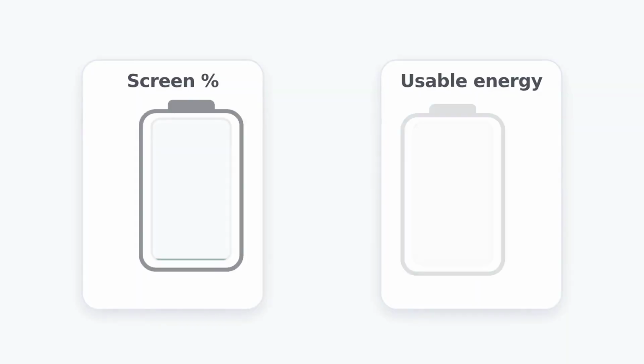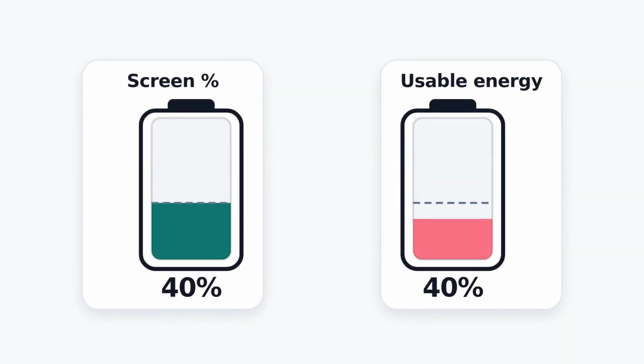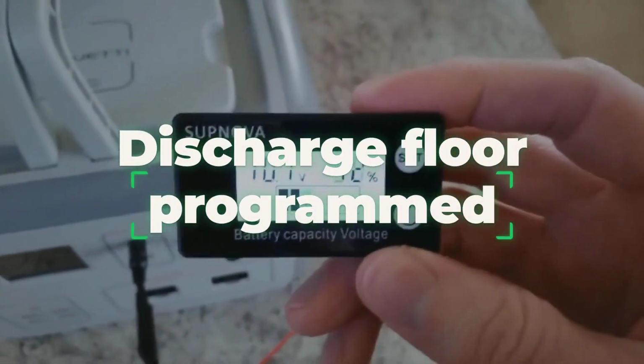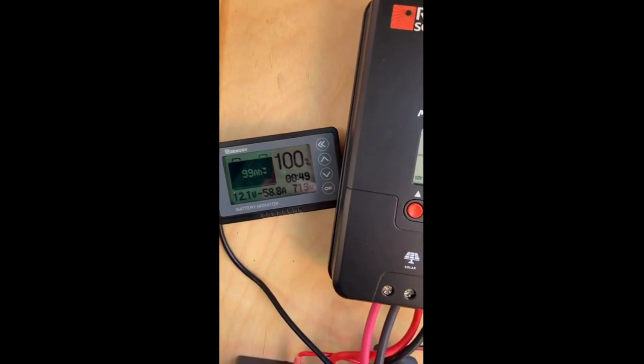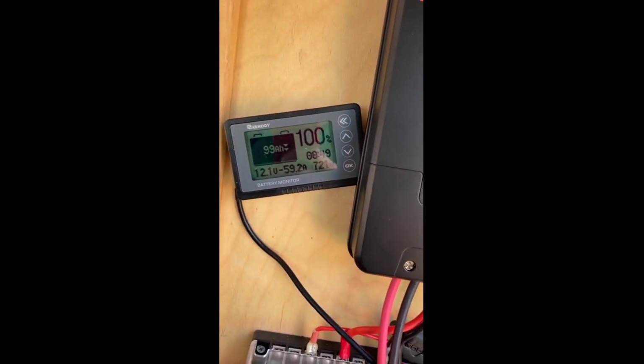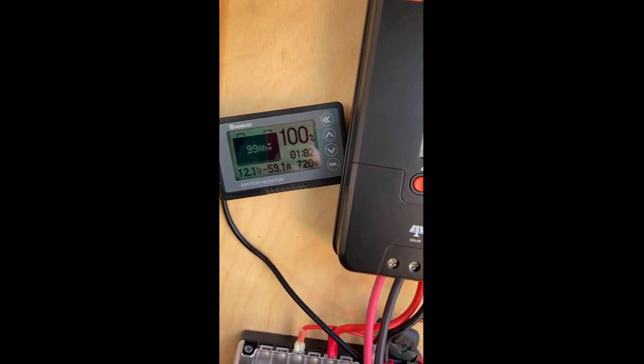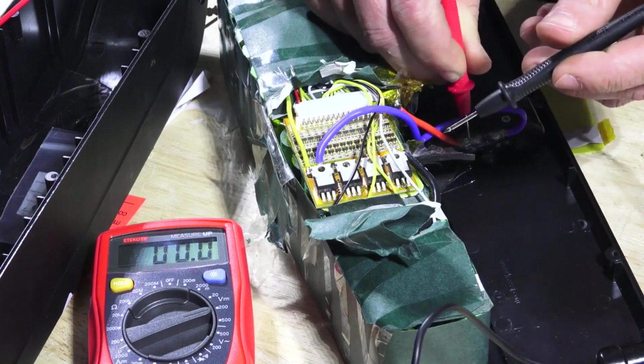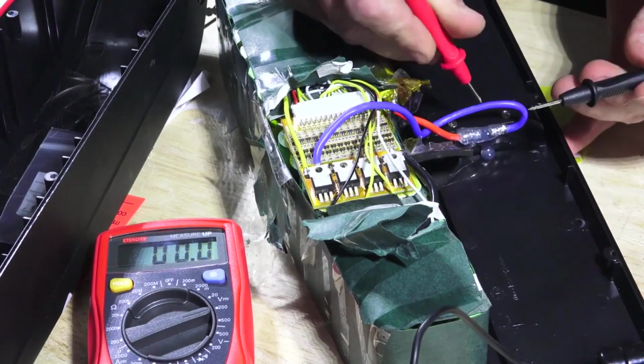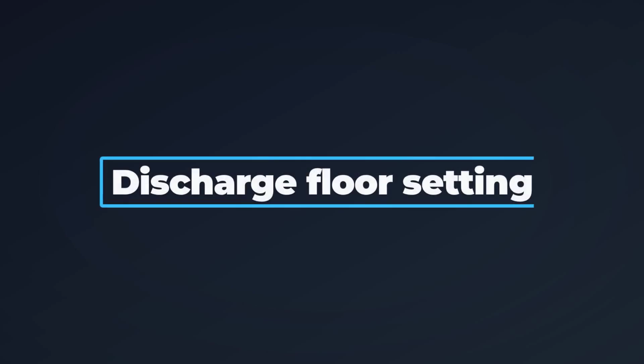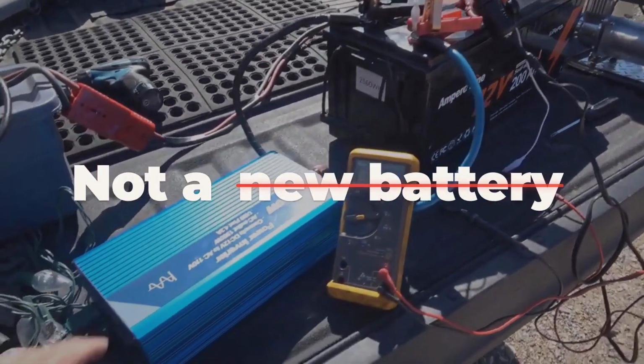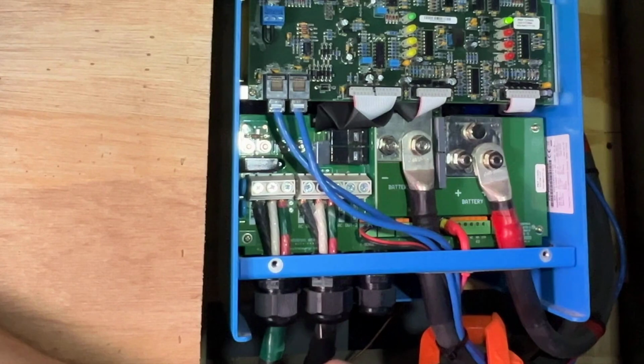Here is the problem. 40% on that screen is not 40% available to you. The BMS has a discharge floor programmed into it, and when real voltage hits that floor, it cuts output, regardless of what the state of charge display claims. This video is a behavior autopsy on exactly that event, and the fix is a specific discharge floor setting, not a new battery, not a firmware rollback. Before we get there, we need to kill the wrong diagnosis first, because most owners waste weeks chasing it.